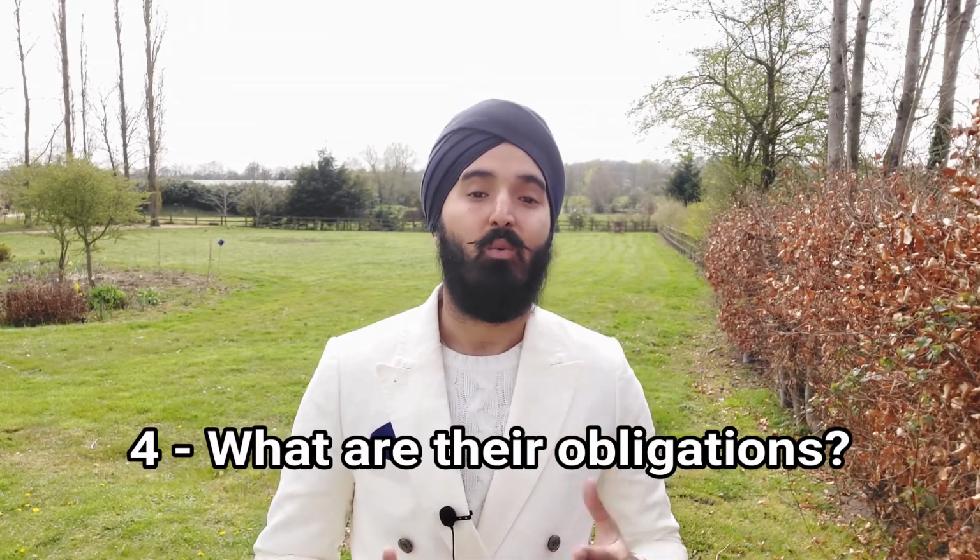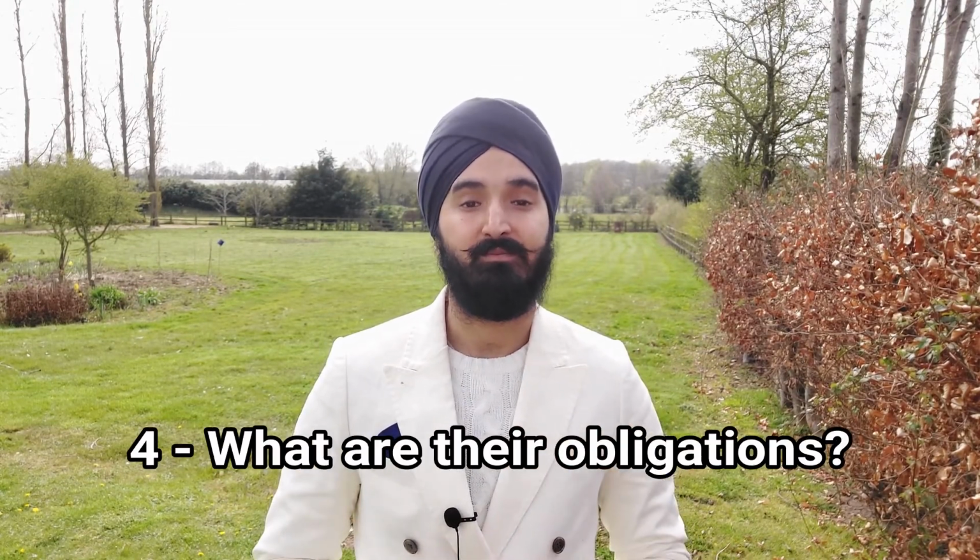Number 4. What are the obligations and duties? Once appointed, an EU Authorised Representative must verify that your EU Declaration of Conformity and technical files are appropriate to the relative conformity assessments. They're also required to keep up-to-date copies of such files and present them to a competent authority in a language appropriate to that member state.